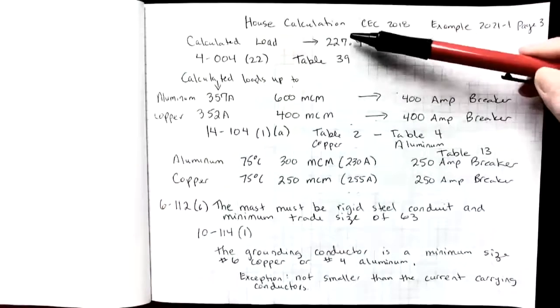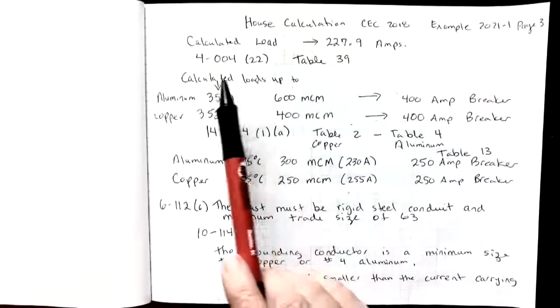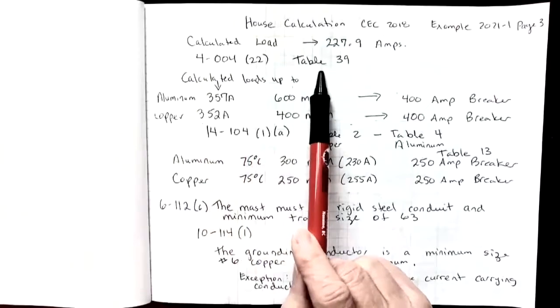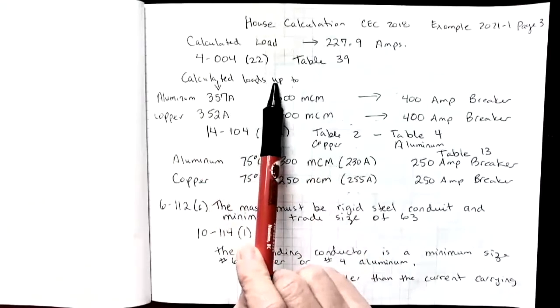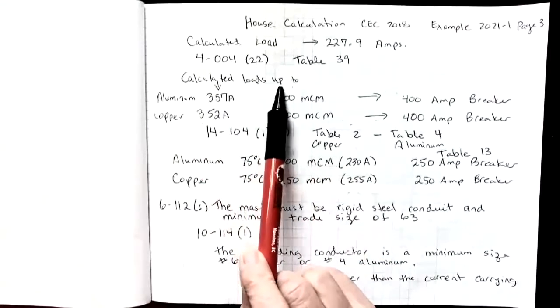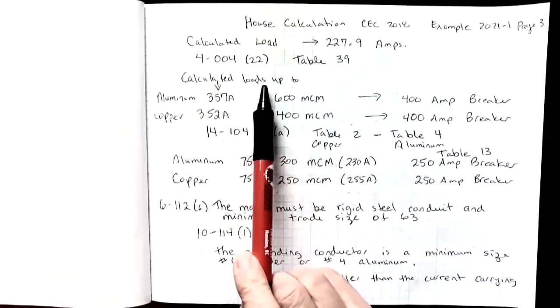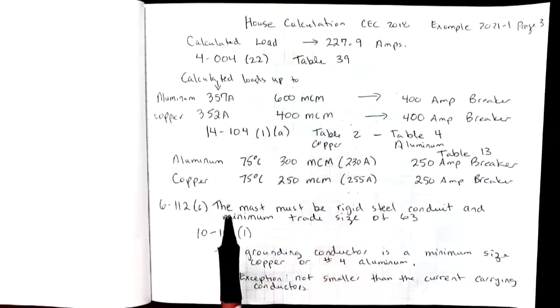Our calculated load at 227.9 amps. We can go using rule 4-004 sub rule 22. We can go to table 39. Use that calculated load to try to find our wire and breaker size. Now I want to also mention that sometimes table 39 gives us a larger number than what would be the minimum. So we're always going to compare the results of table 39 with the results of table 2 or 4 and table 13. And I'll get to those in a minute.